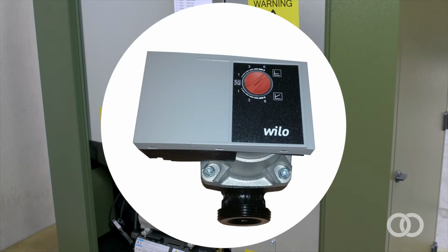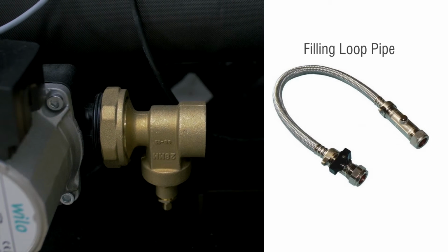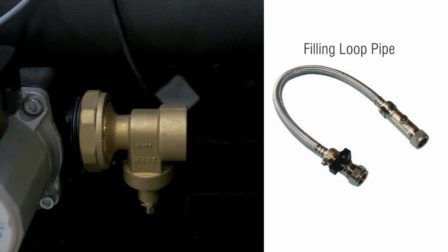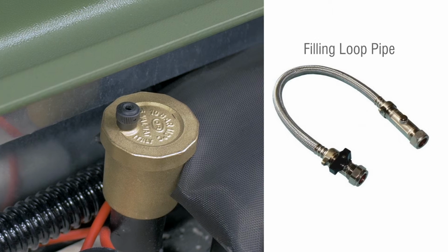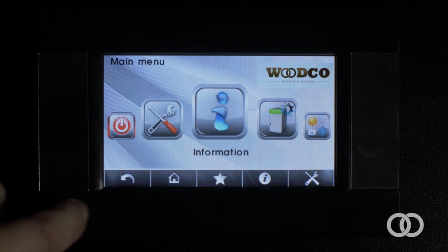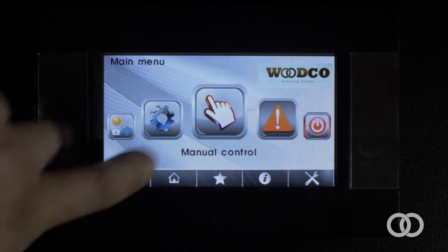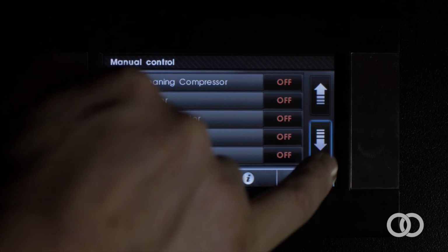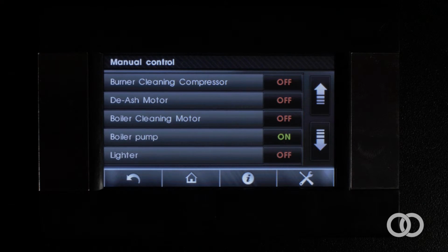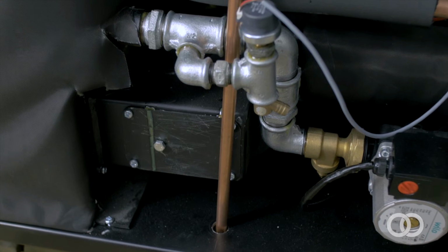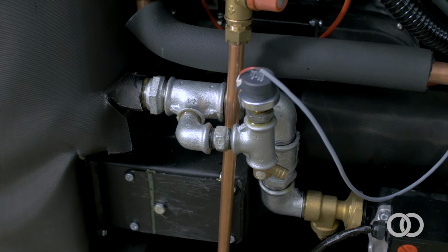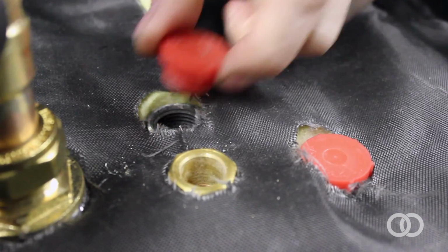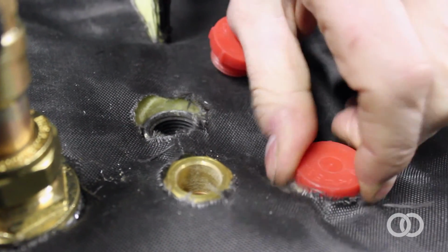The boiler is fitted with an energy-efficient variable speed pump. The system should be filled from the lowest point on the heating system to force the air to the highest point where it can be vented. To de-aerate the system, enter the manual control menu and activate the pump. Repeat the procedure to turn off the pump. Only when the system is fully vented can one commission the boiler. Always ensure the fittings are tight and sealed when filling the boiler. Remove any red caps and blank with plugs if not used.